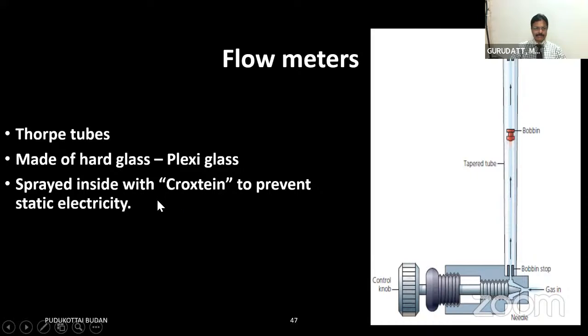So that is mainly to prevent static electricity. When the bobbin rotates, the rotation of the bobbin will induce electricity there. Once the electricity is released, if it stays there and becomes static, it makes the bobbin stick to the inner wall of the flow meter. Once the bobbin is stuck, you don't know what the flow of gases is. So in order to prevent that, the Croxtein is sprayed inside.